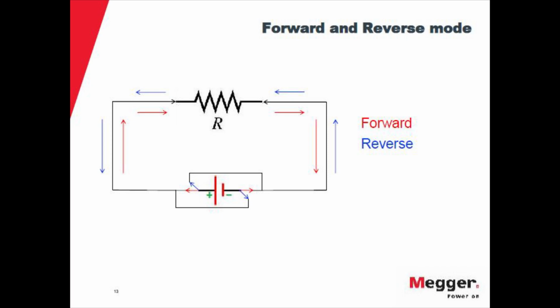Yes? In the 4-wire measurement, how do you eliminate potential induced voltages that you're unaware of? Induced voltages, magnetically induced voltage. So basically you are averaging, or you are considering the effect in one direction and subtracting it from the other direction, and then you get your actual result. One easy way to see this is when you are performing measurements of strap resistances in batteries. In batteries you will have current flowing in this direction, so that will affect your measurement, but then you measure in the other direction and you get a reversed measurement, and you subtract or average that, and you get your result.